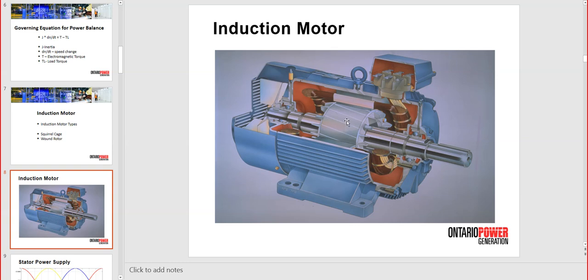We have double cage. Another special motor can be a multiple speed motor for traveling screens, and that is done through multiple coils in the stator that change configuration to get different speeds of the rotating field, and the cage will follow. For instance, for 1800 RPM, 2 pair of poles, we will have 1750, 1780 maximum rated speed of the shaft. There is always a slip between the rotating field and the shaft speed, because otherwise there is no induction in the bars. So that is the condition for the induction motor to operate. The higher efficiency motors have less required slip for the operation. The lower efficiency ones, like deep slot and double cage, will have larger slip, larger losses.